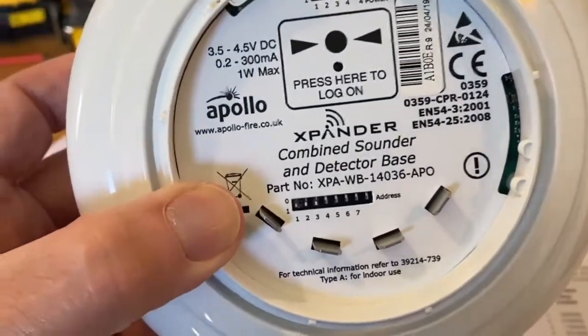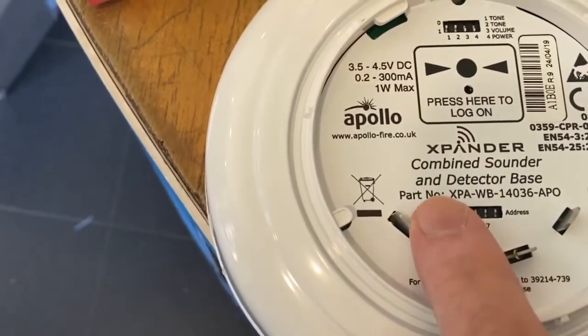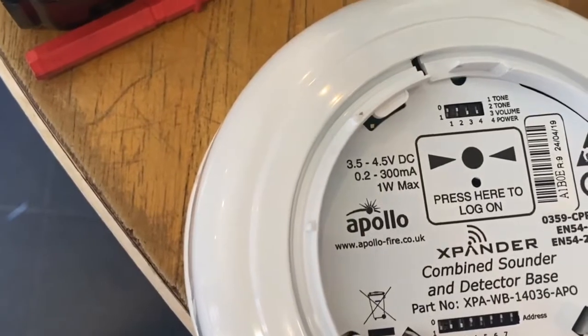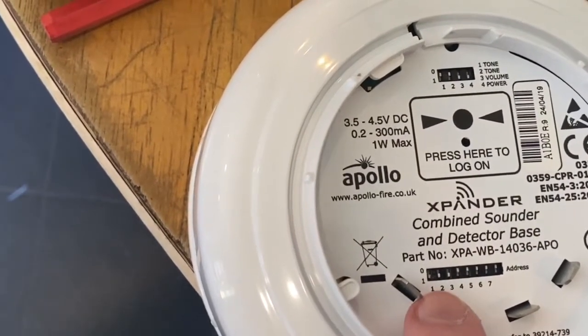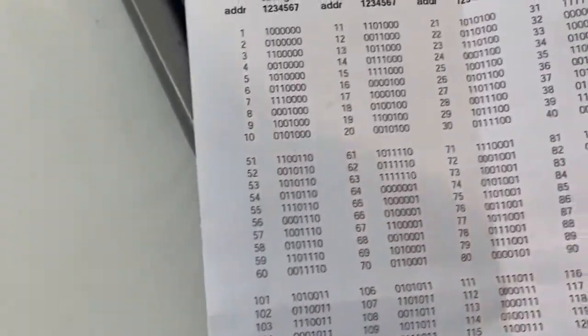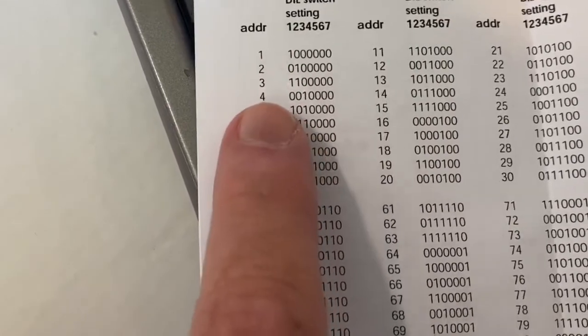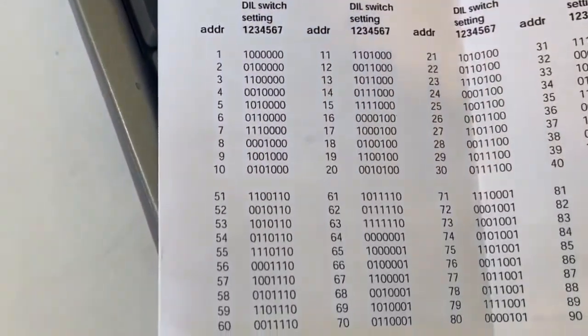I'll quickly explain the addressing used on these, because it uses binary. The switches are numbered one through seven. Binary works in powers of two: switch one equals one, switch two equals two, switch three equals four, then eight, sixteen, thirty-two, sixty-four. So if you want address three, you turn on switches one and two. For address four, you only turn on switch three. For address five, you turn on switches three and one. It's easier to use the Apollo guide that comes with the equipment - it lists: one is switch one on, two is switch two on, three is switches one and two on, four is switch three on, five is switches three and one on. A little confusing at first, but once you get binary in your head it'll be easy going forward.